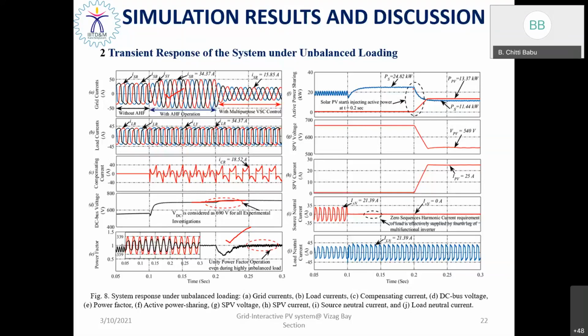And this is the active power sharing, where the 24.82 kilowatts of grid power has been reduced to 11.44 because the PV is also contributing to the load demand, about 13.37 kilowatts, so that it ensures proper power sharing. And moreover, as we use a three-phase four-legged inverter, without the controller on this inverter, there is a strong circulation of the neutral current of the inverter.